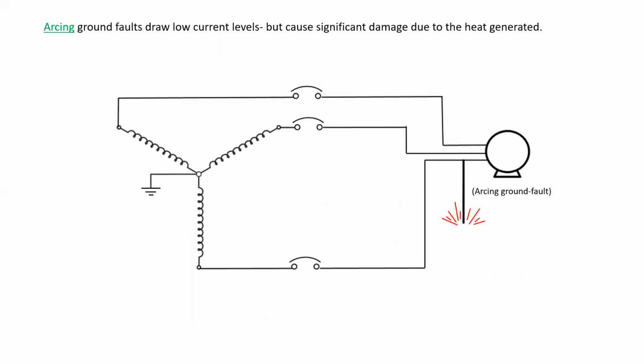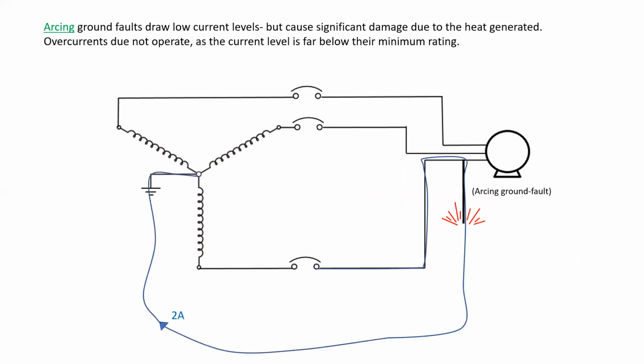Arcing ground faults draw low-level currents, and this can cause significant damage due to the heat generated. If the current flow is too tiny, it means that the overcurrent will never trip, even though there is significant damage taking place. So only 2 amps flowing, but causing an intense heat event in one particular location, if the conductors are inside a metal conduit, at some point, if only one of them is ground faulting, it may cause damage to other adjacent conductors in the conduit.